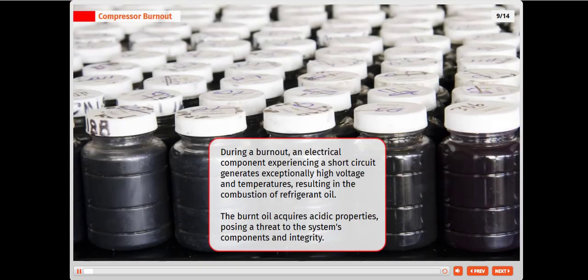During a burnout, an electrical component experiencing a short circuit generates exceptionally high voltage and temperatures, resulting in the combustion of refrigerant oil. The burnt oil acquires acidic properties, posing a threat to the system's components and integrity.